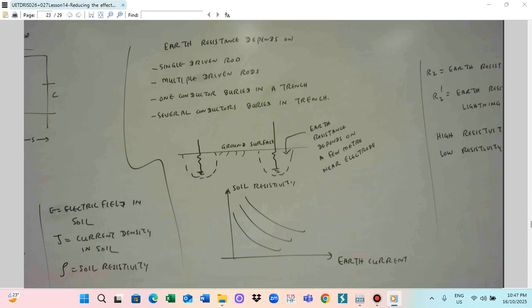Now we can also utilize this for the earth resistance. Earth resistance depends on the number of rods driven into the ground. The more rods, the lower the earth resistance. Whether you use only one rod or multiple driven rods, or one conductor buried or several conductors buried, it depends on the number of buried conductors. For example, with several buried conductors the earth resistance will be lower, and with multiple driven rods the earth resistance will be lower than with a single driven rod. This is similar to resistors connected in parallel: when you use resistors in parallel, the resistance will be smaller.